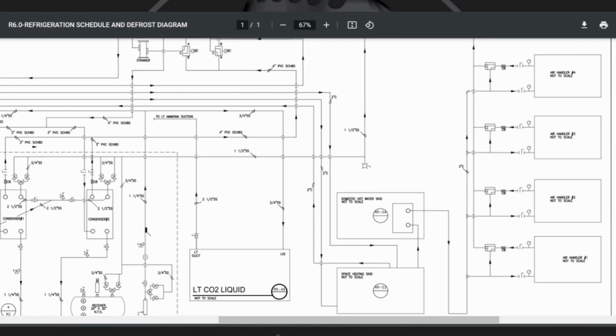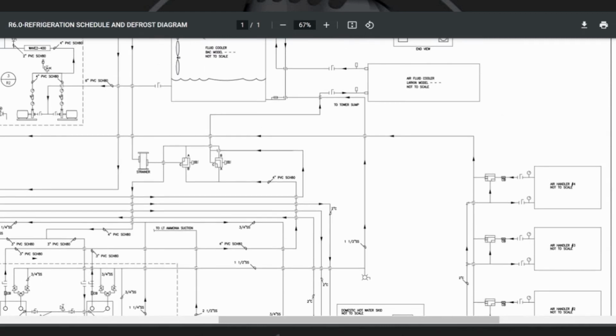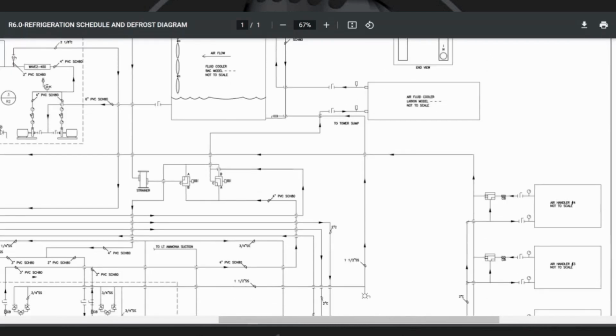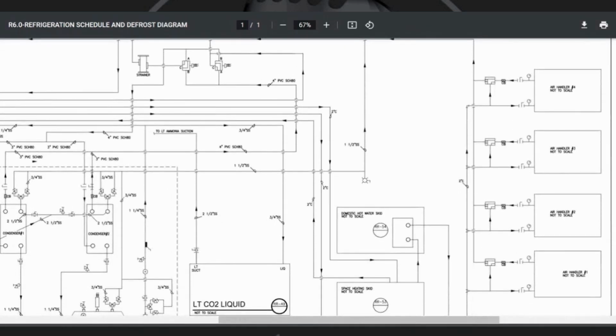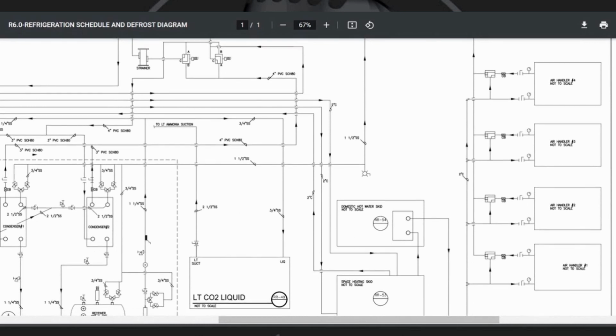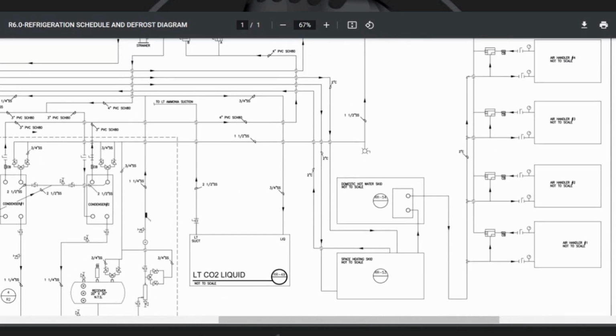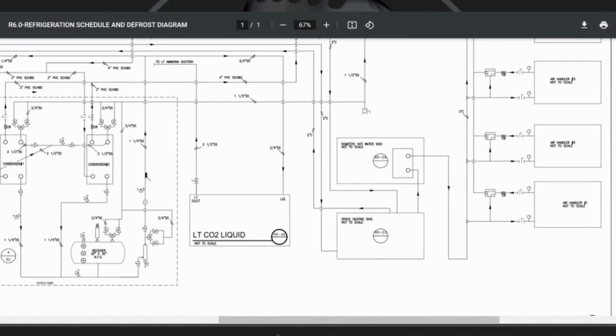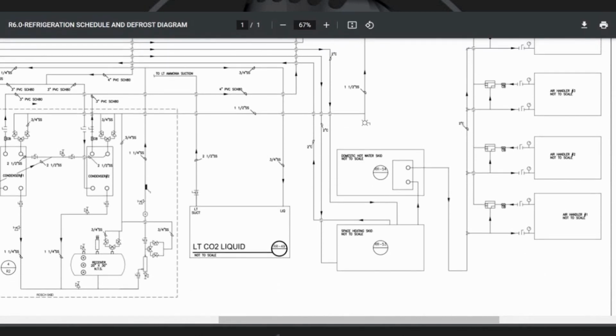Gotcha. So on this site, there's no synthetic refrigerants at all, no self-contains, no nothing. It's straight ammonia CO2, correct? Unfortunately, I missed something I didn't know about. The owner of the building put an air conditioner in the elevator shaft. This has a 2-story mezzanine, and the air conditioner in the elevator shaft is synthetic refrigerant.